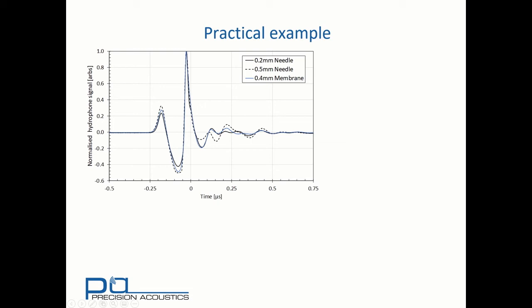This peak negative excursion eventually relates to peak negative pressure, and peak rarefactional pressure is of critical importance when determining the output of a diagnostic ultrasound machine. In this case, we can see the variation is up to 25%.